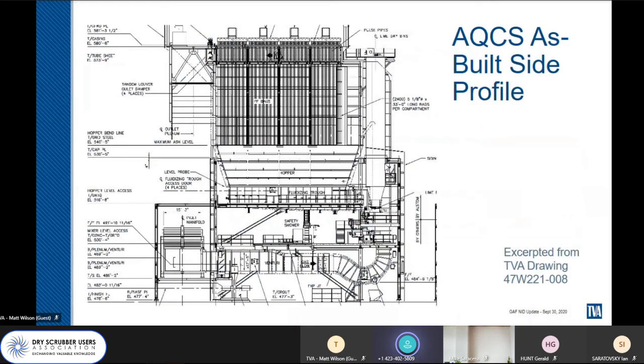Here's an excellent side profile view from our TVA drawing. So again, this is from the back side, I guess, angle instead of those construction view angles. Here's our inlet manifold. Here's our venturi, which is essentially a flow nozzle of the flue gas. We got pressure transmitters on either side of that venturi section.